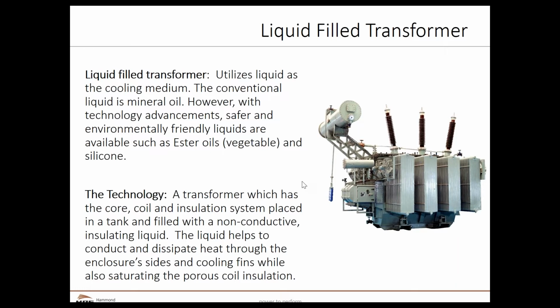When the transformers are cooled, with the cooling fins here, there may be some pumps or there may be natural convection flow for those fins to help dissipate the heat. In some cases, the fins are very small and they're just trying to extend the surface area of the enclosure. So the fins have different technologies, but you can also think of them as a radiator for an oil transformer, and it is an additional thing that does have to be maintained and could be damaged or could cause a leak as well.